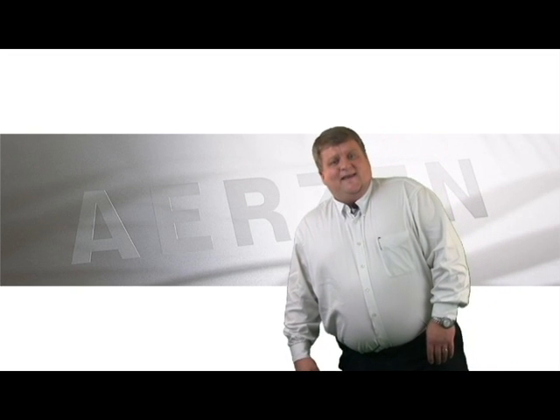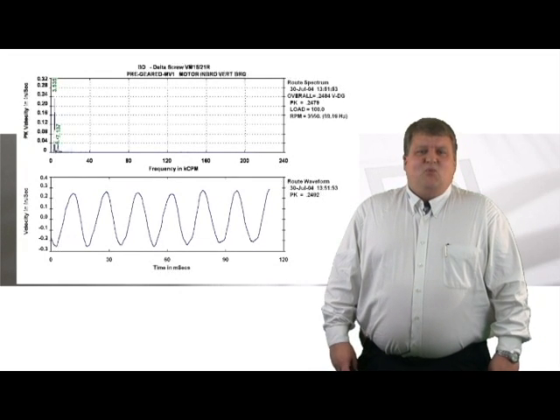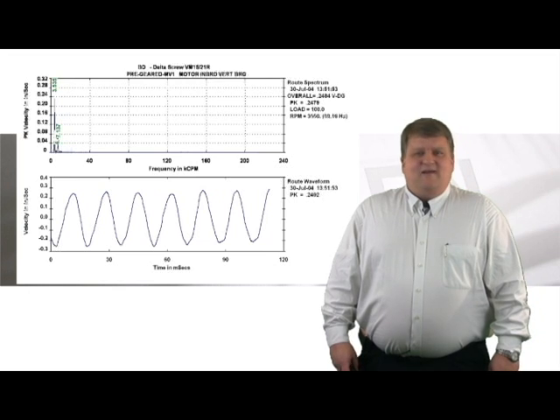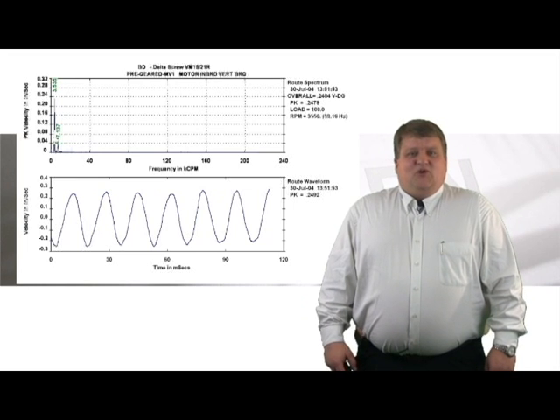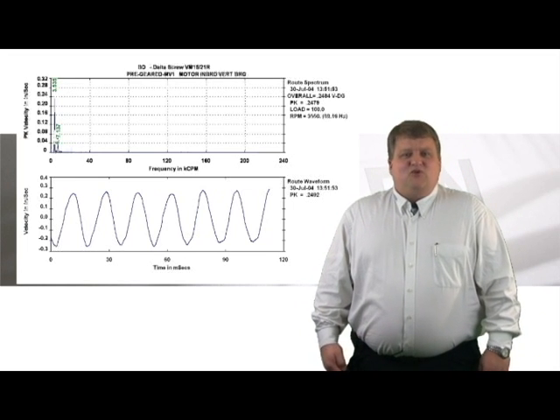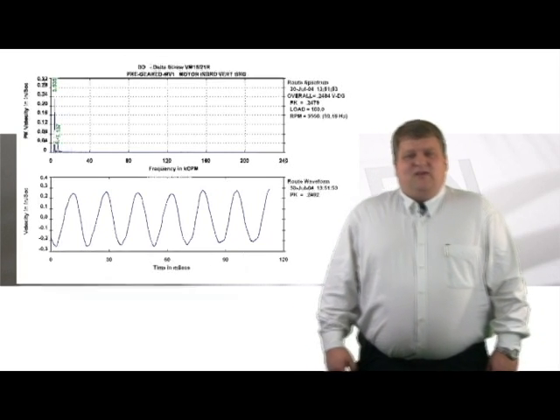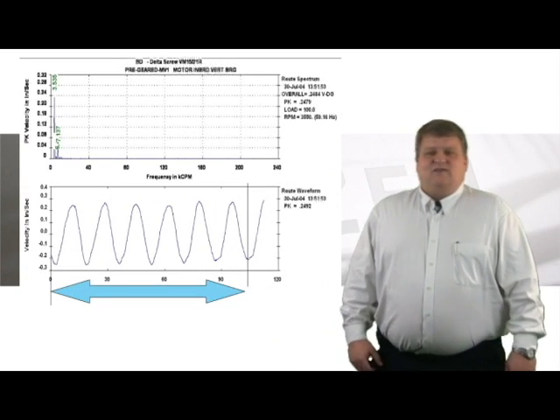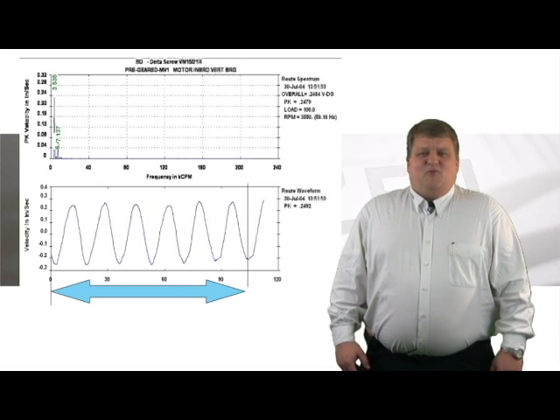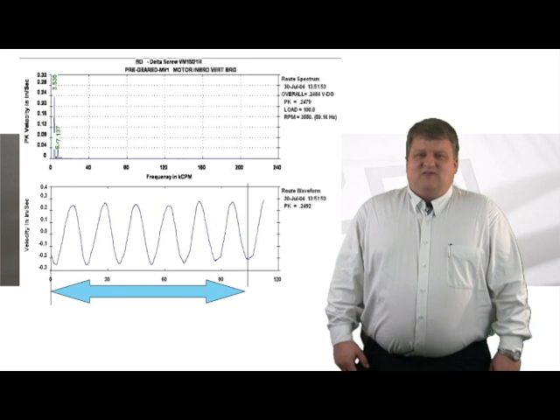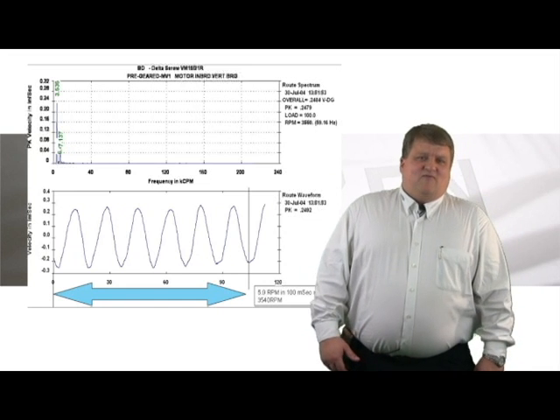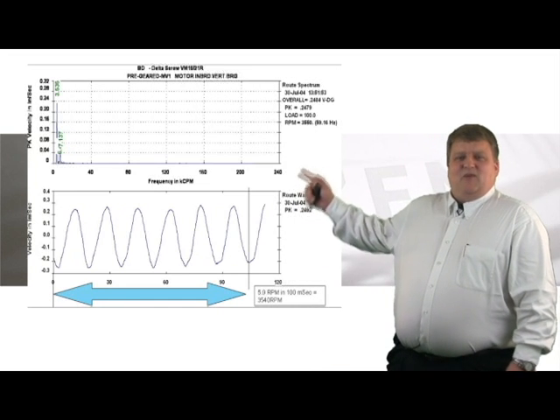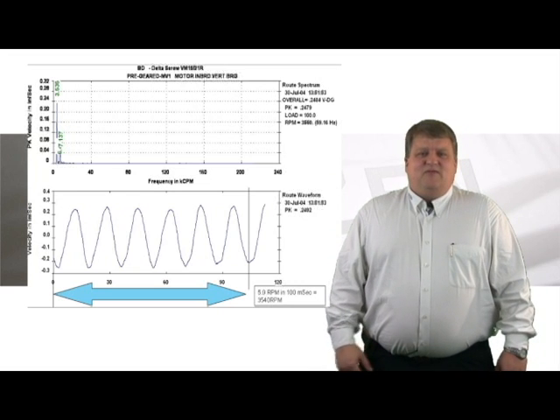Here I have a practical example. I used this on a motor that I captured with vibration analysis equipment. You can clearly see and identify the time waveform at the bottom, nice squiggly line. Up on top, my FFT shrinks it down to manageable data, saying this is the time frame in a hundred milliseconds. This one traveled almost 5.9 times per hundred milliseconds, which when you calculate it up, it's 3540 RPM.